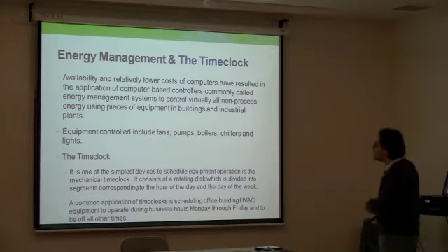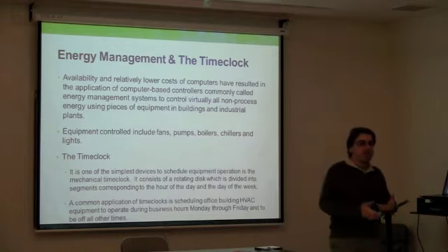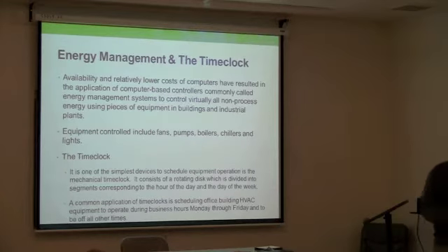time clock, depending on what kind of operation you want on the motor, and make sure the motor is operating at the required time. Many times I go and I audit, for example, a factory, and I see the compressor is working all the time, 100% of the time. It's working. And it doesn't make sense because you look at, there is no usage of the vacuum, pressurized air. Why is the compressor working?